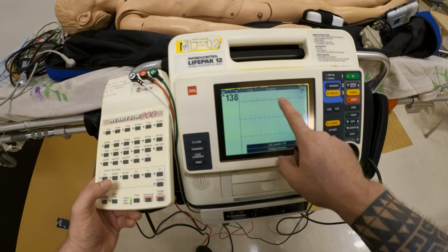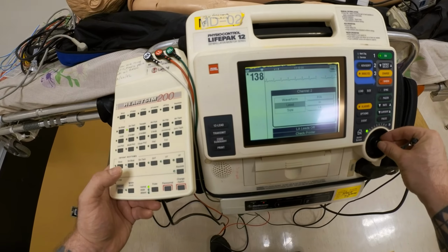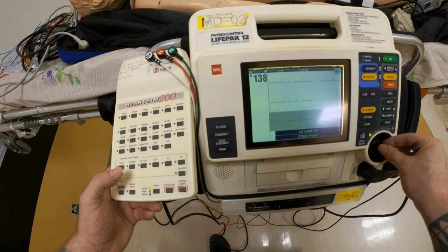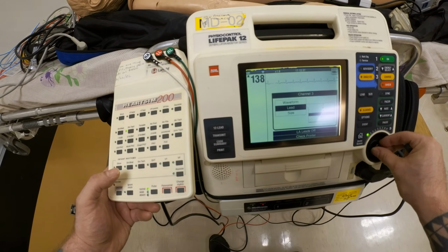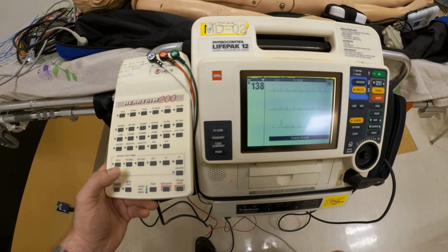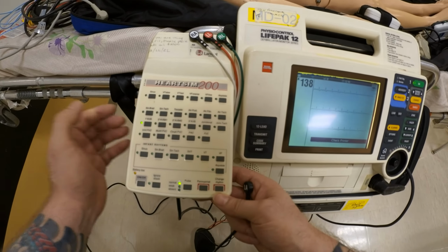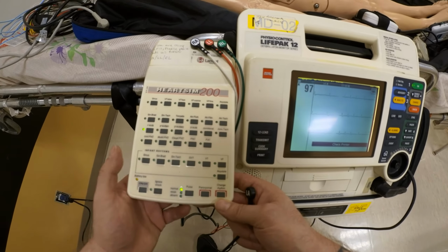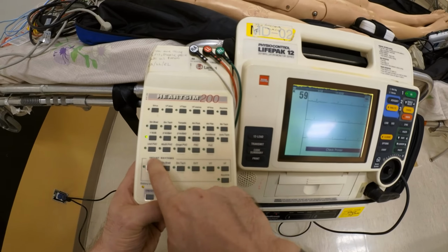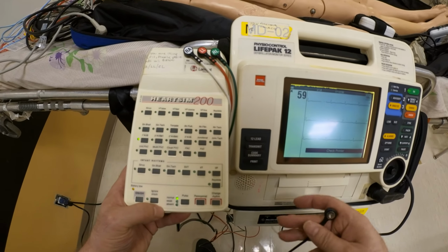And you notice, right, I only see lead 2, and the other leads are not displayed. So one way you could remedy this is basically make all leads lead 2. And now you have everything displayed. Right, so everything is lead 2, and you could essentially change through your rhythms, right? And you see, right, the appropriate rhythms now show up on your monitor. You also have infant rhythms. The rates will be higher than the rhythms for the adults.